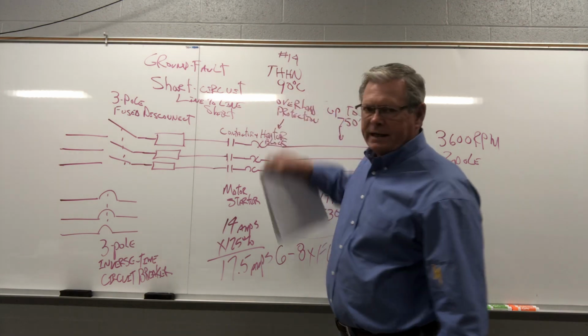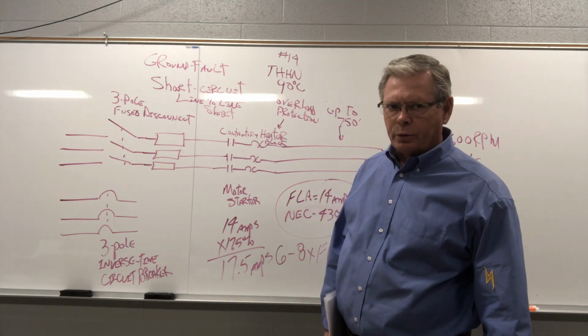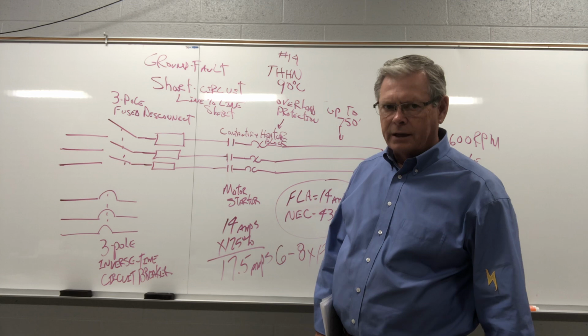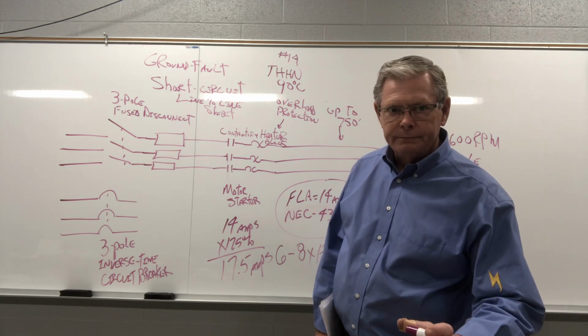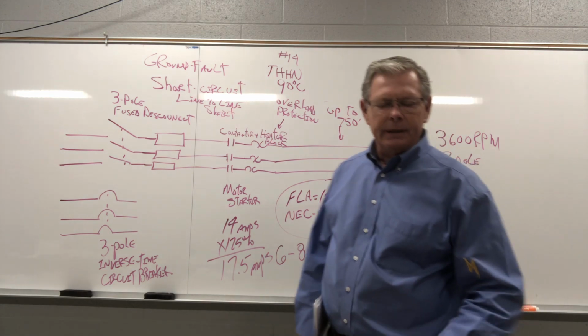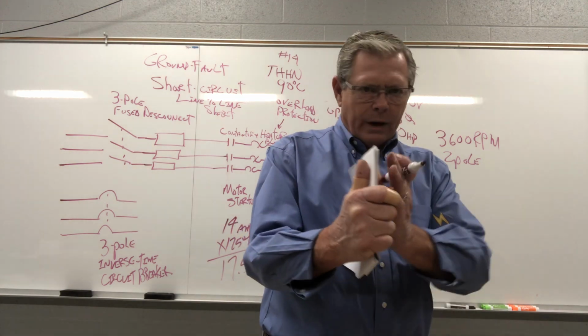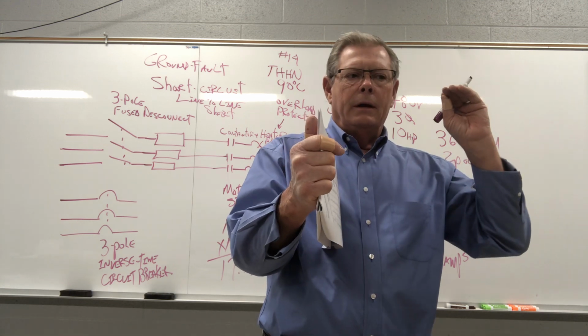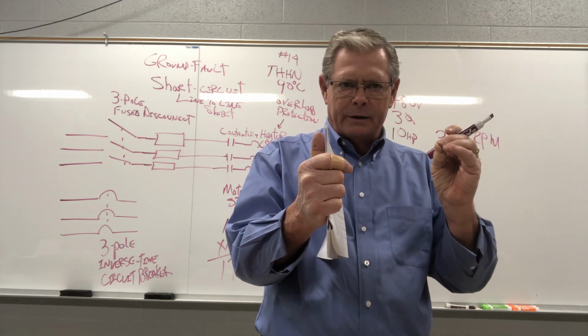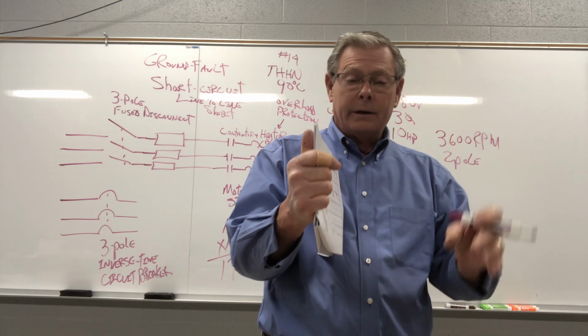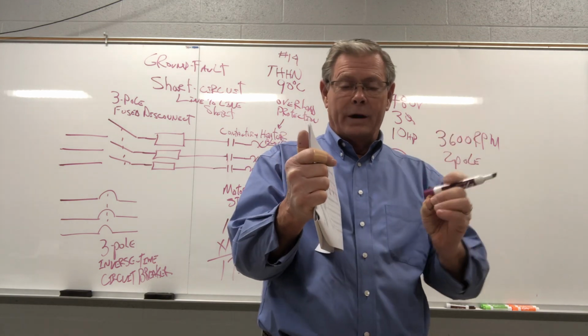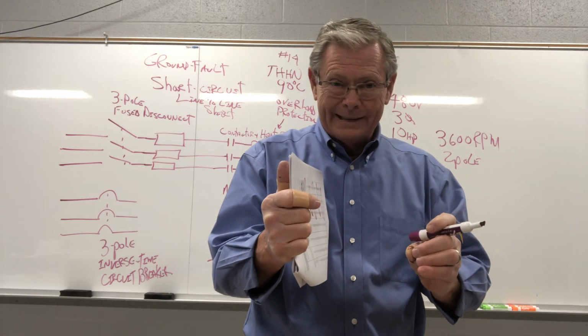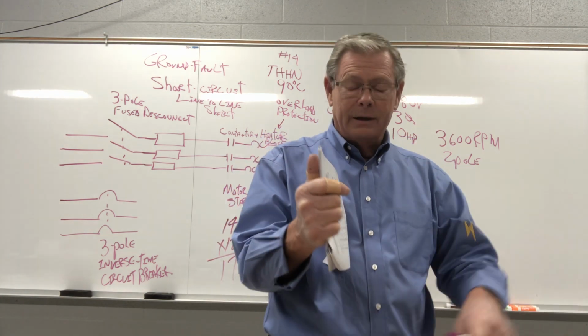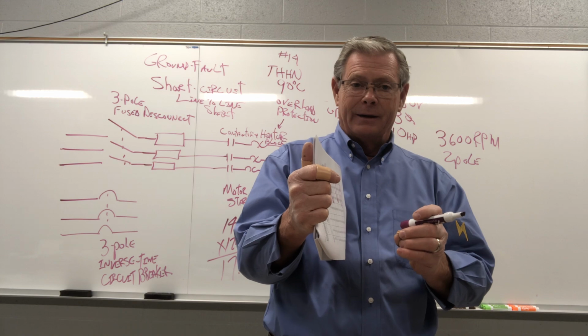Legally, 14 THHN, we could put on a 25 amp breaker if we had to, okay? On a motor, only on a motor. If you're out anywhere else other than motors, everything else in the code books, if you see 14 gauge wire on anything bigger than a 15 amp breaker, it's wrong. Other than a motor, if you see 12 gauge wire on anything bigger than a 20 amp breaker or fuse, it's wrong.